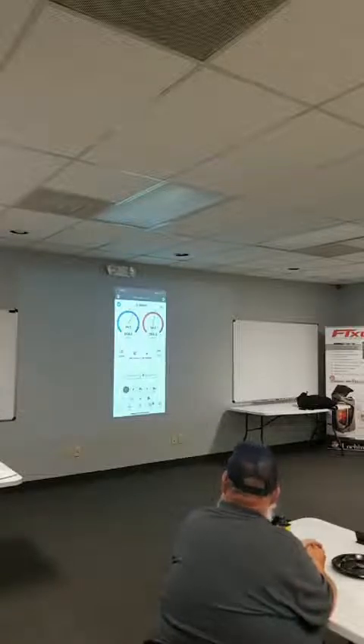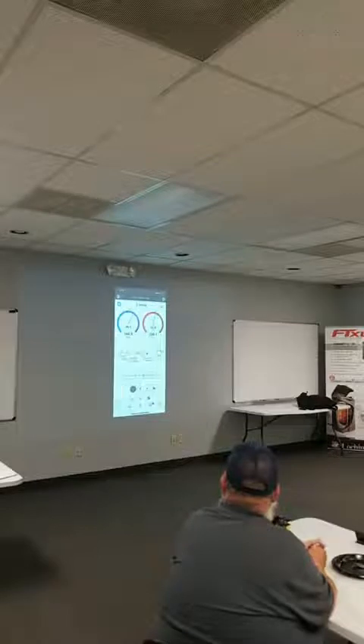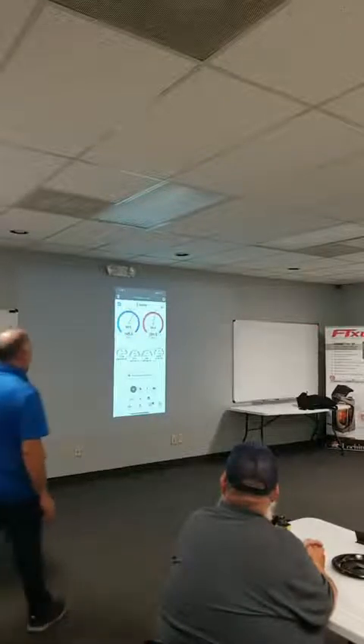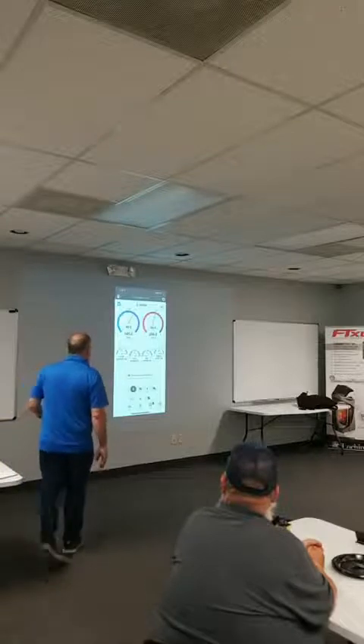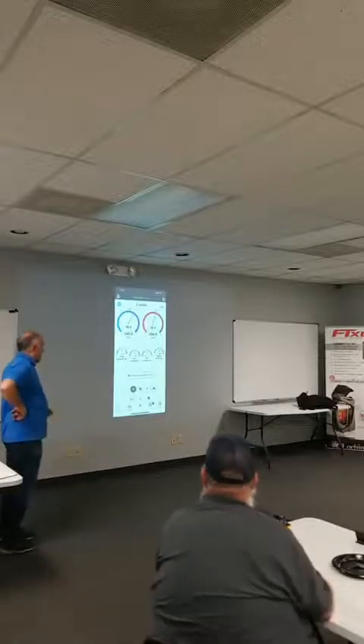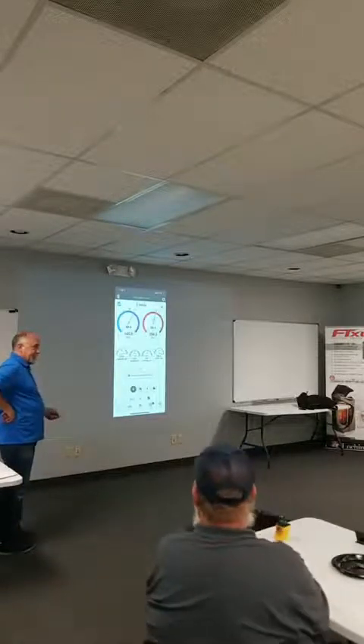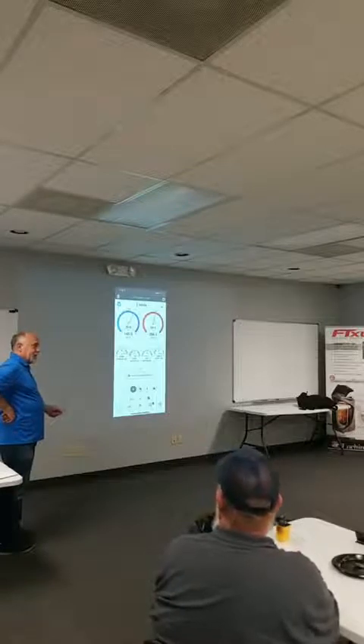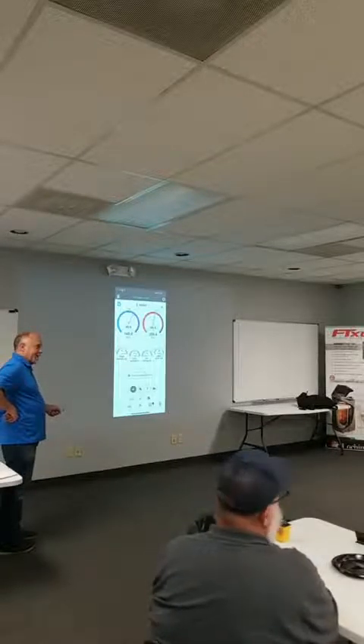No. This is the one that when we first ran Measurequick on it, subcooling was extremely high. Kevin and I pulled the charge out and weighed it back in, and it was virtually the same after it ran for 10 minutes. Now this is another mistake, this is another reason we're getting some wacky readings on here. Whoa. What can you tell me about that liquid line temperature? Everything's high. Way too high. It's on the discharge line, not the liquid line.